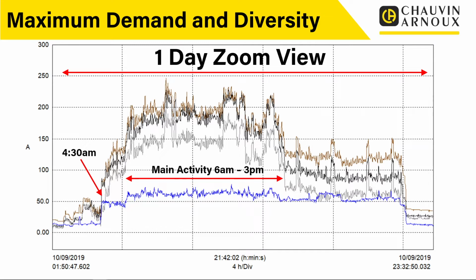But realistically, the loading generally tends to be under about 200 amps all in. It does go over that, but not for huge periods. Again, we'd probably want to zoom in and have a look at those bits where it's gone over, just to see how much over for how long, if we're making decisions on what we're going to allow for diversity. Then we get a period between about 3 p.m. and 10 p.m. where the load seems to drop again, but doesn't disappear entirely. And then after 10 p.m. it's pretty quiet in there.